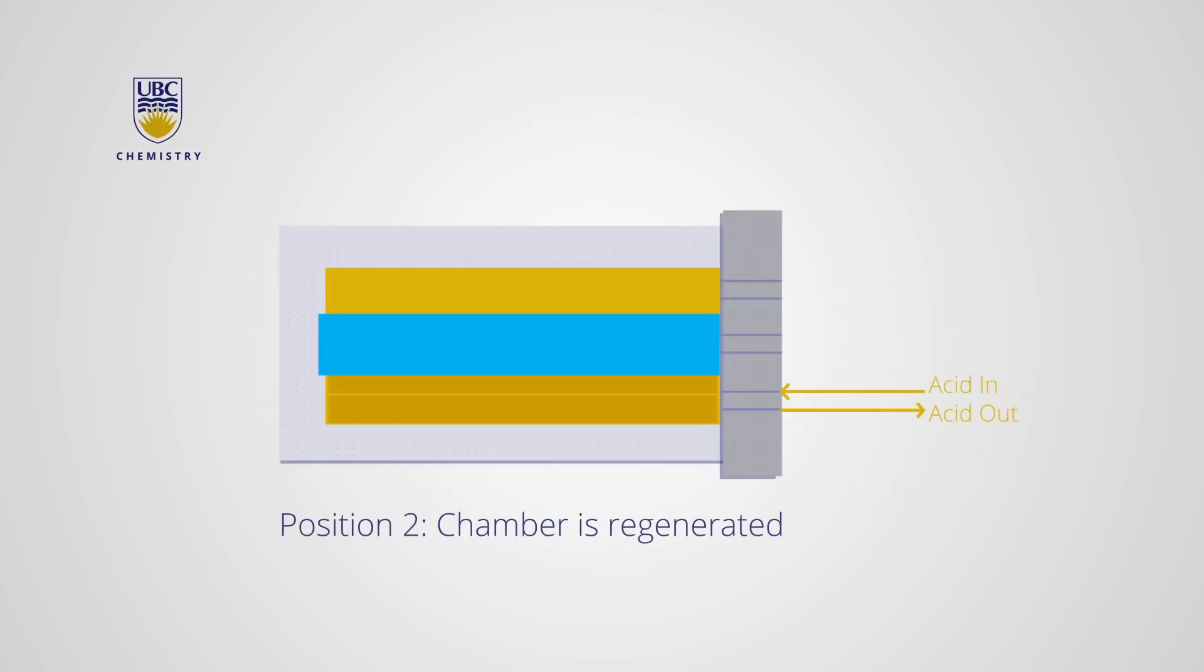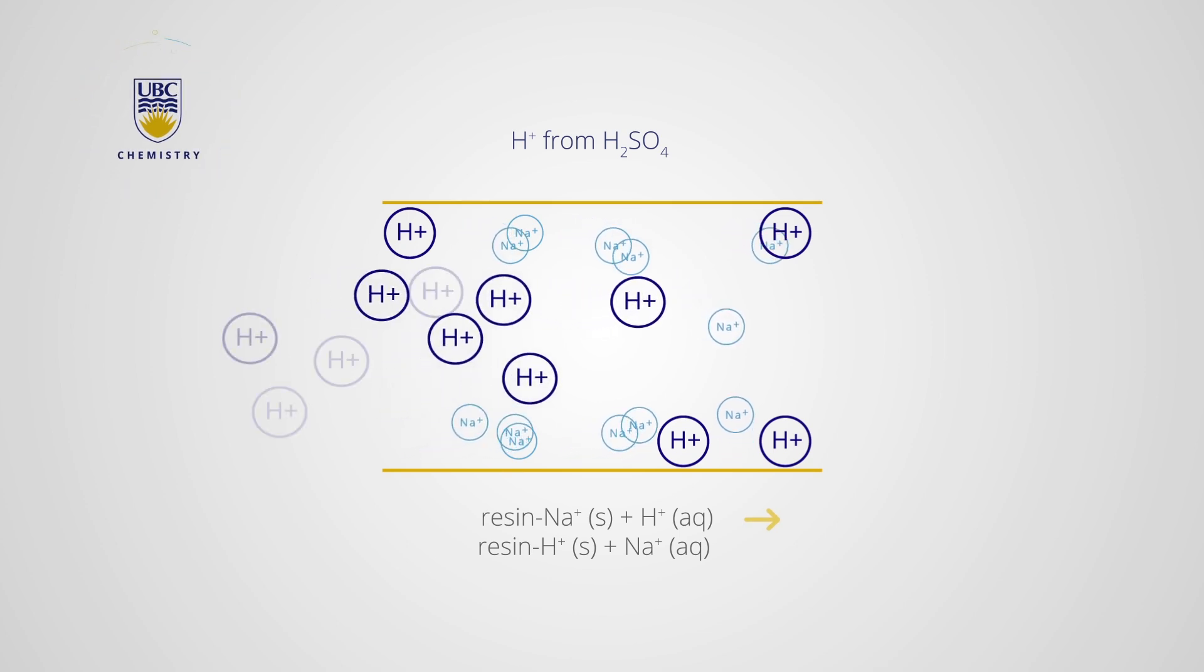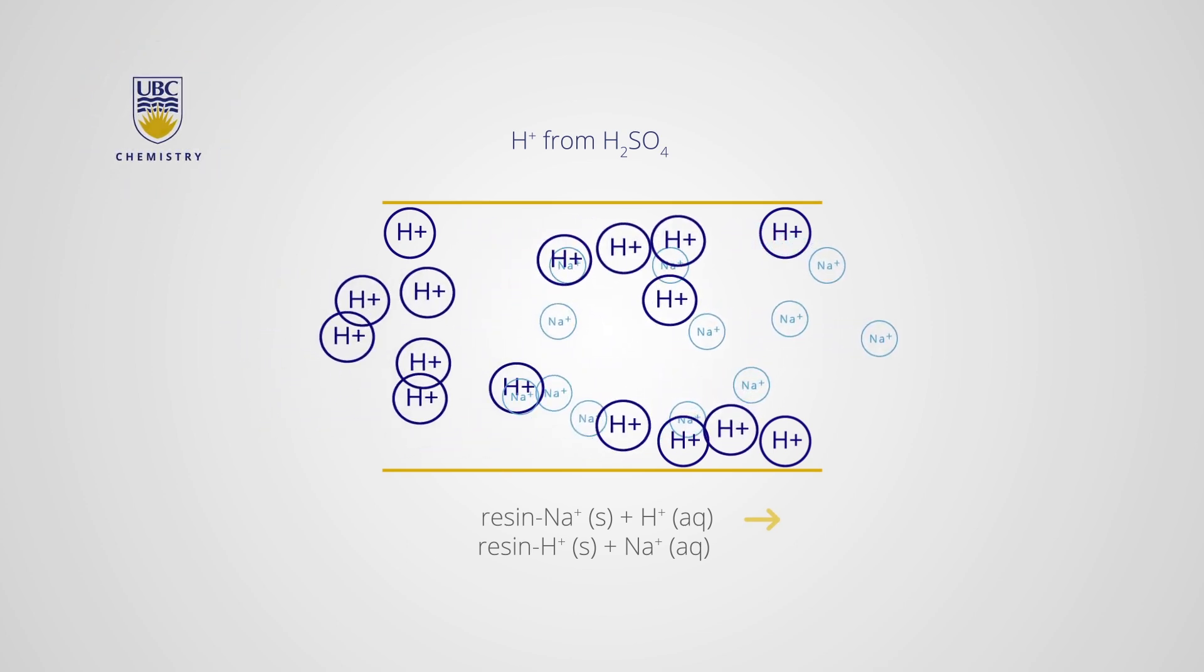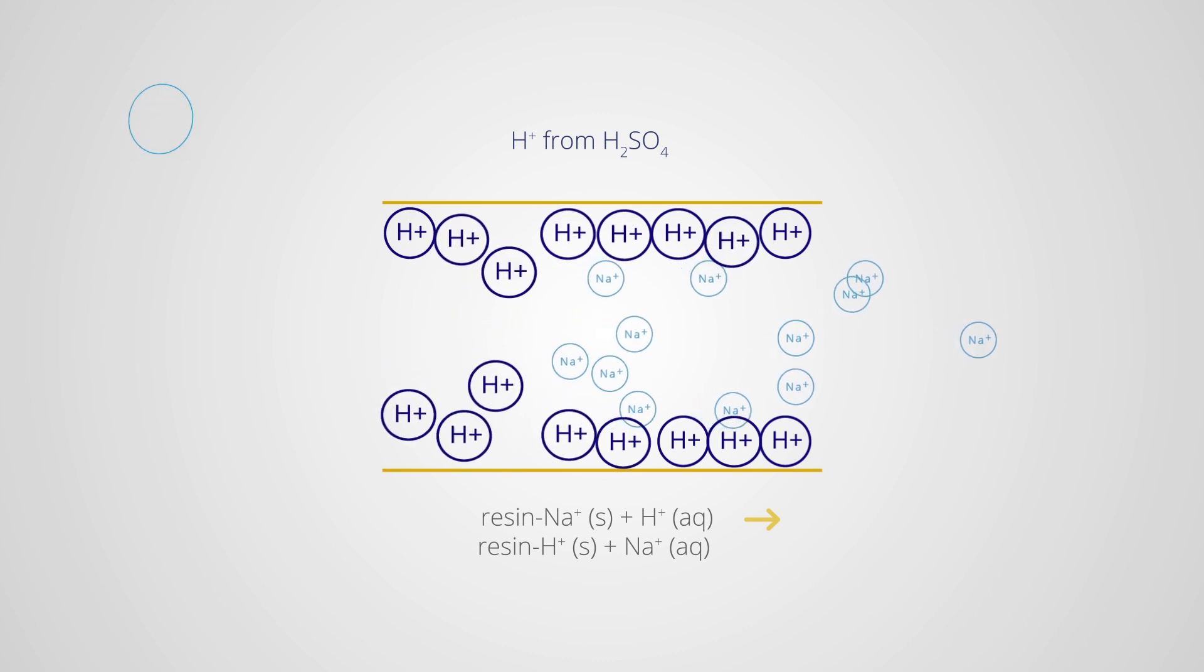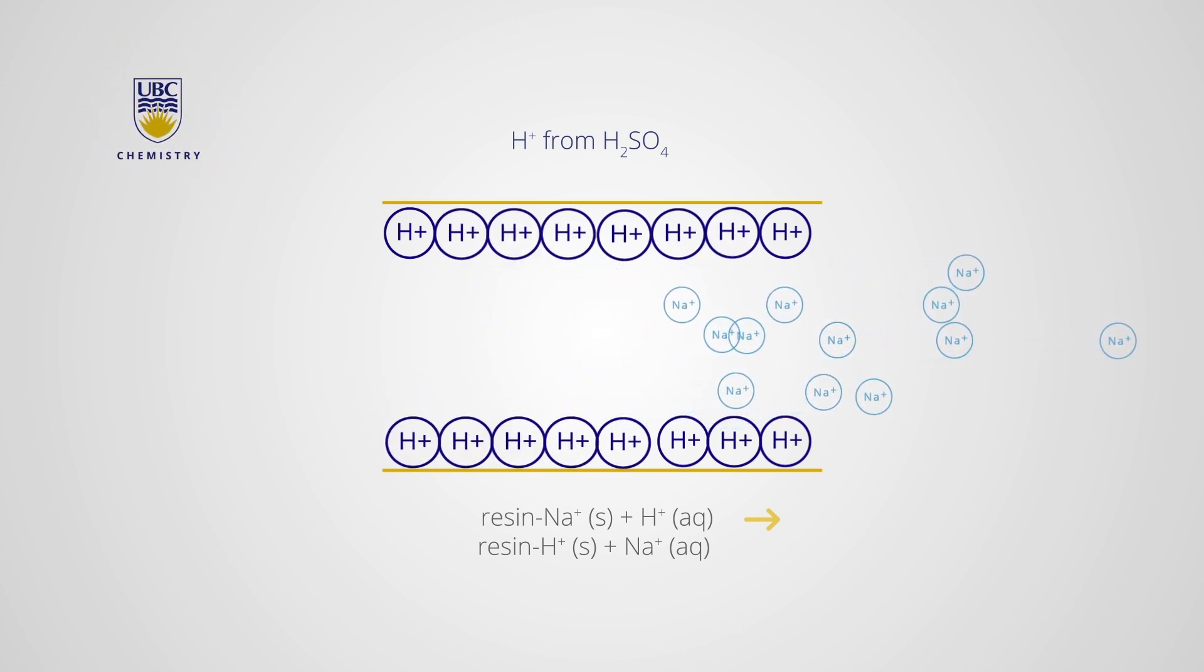Once the conversions are complete and the analyte anions are detected, the next step in the suppressor sequence commences. In the second step, the chamber moves to its next position, where it is subjected to a regenerating solution of sulfuric acid. A proton from the sulfuric acid replaces the sodium cation on the cation exchange resin. This allows for the resin to be transformed back to its original form.